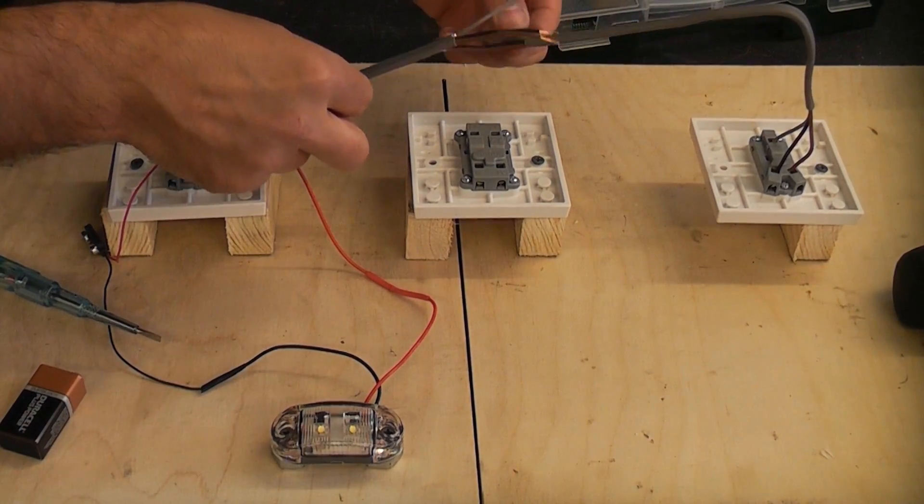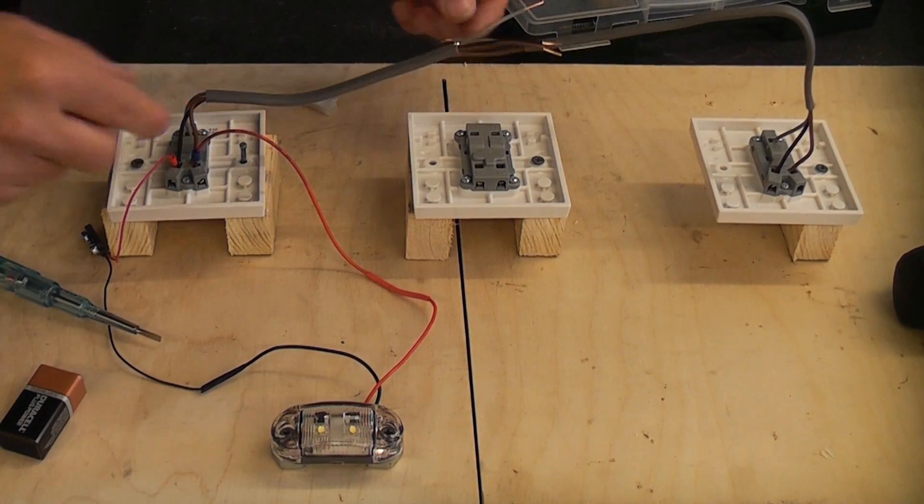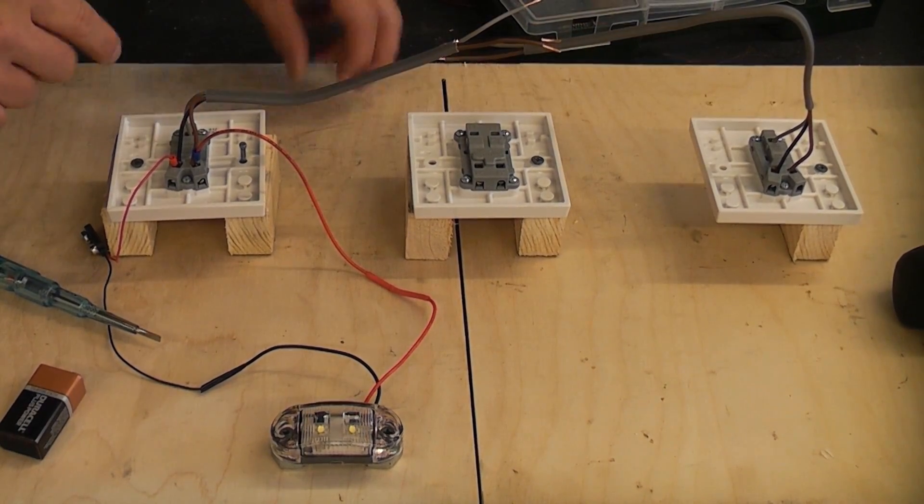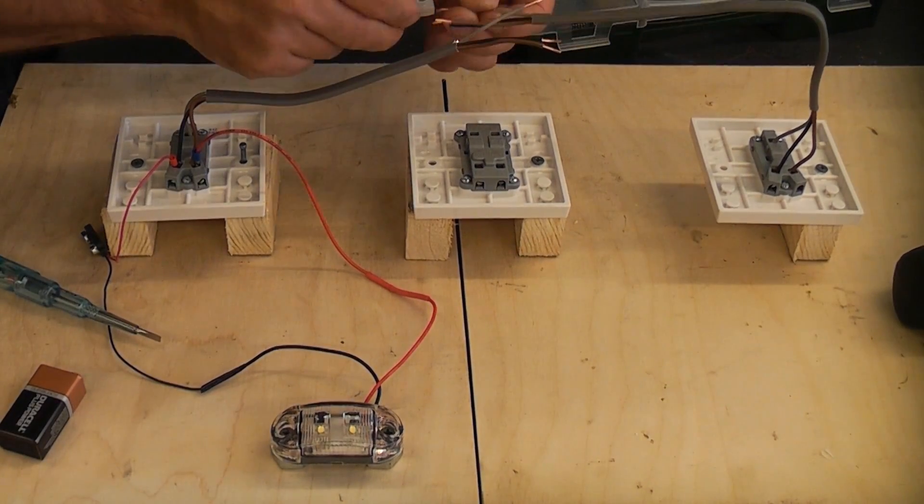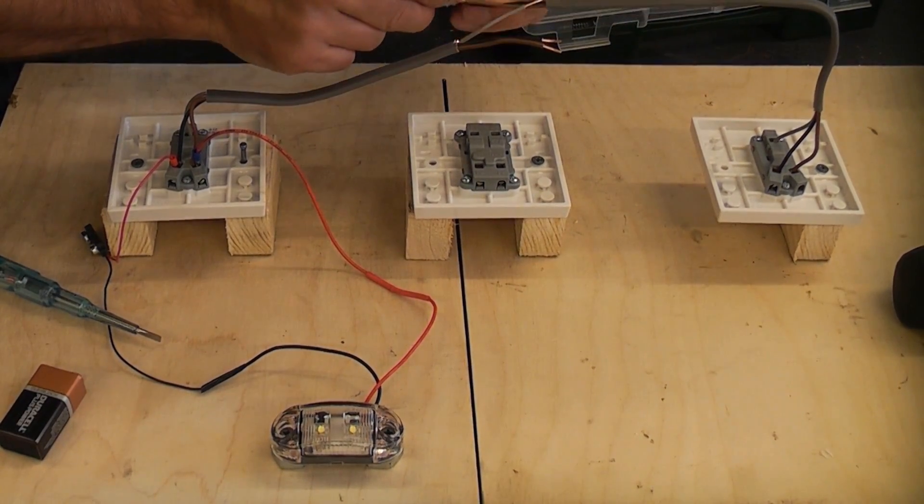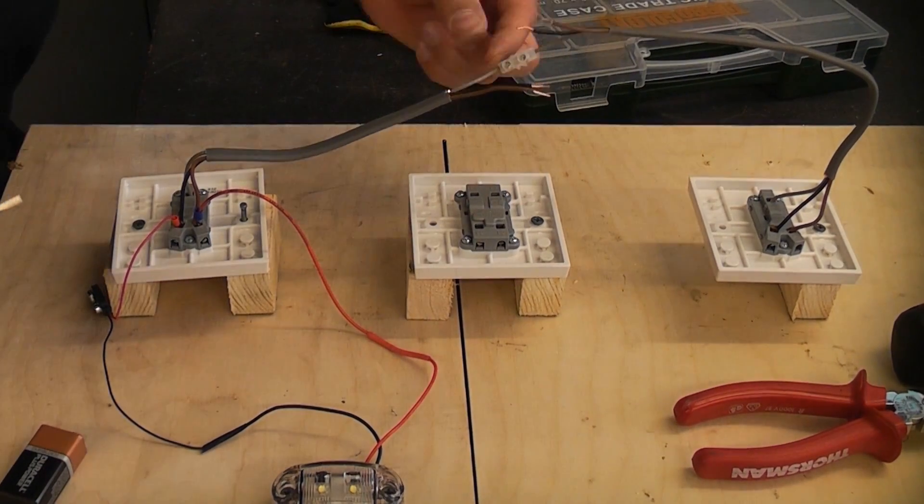We've now got the two cables that have been run to the intermediate switch. The first thing we're going to do is we're going to join the two comms together. So we need to get a terminal like that and in there we're going to put the comm from both of the light switches. So the comm wire now goes straight through.